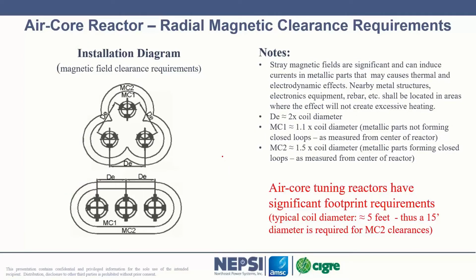When you do look at air core reactors, this goes back to the situation of eddy current heating in the fence, as well as step voltage in the fencing around a filter design. Air core reactors do have magnetic field clearance requirements, often quoted as MC1, MC2. These are multiples of the coil diameter as we show here. These are just typical numbers, but what it does is increase the footprint of the design, because I cannot put a fence inside this area, or other large metallic parts forming closed loops. So incidentally, air core reactors typically take up more space because of the external magnetic fields.